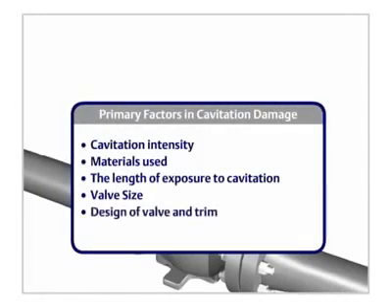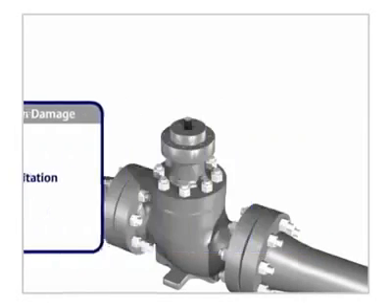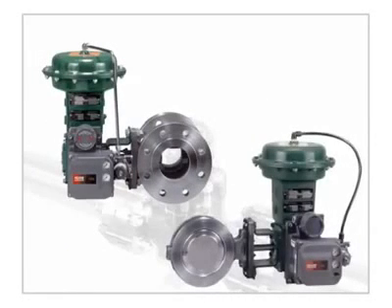The design of the valve and trim in the area of cavitation. High recovery ball and butterfly valves are more susceptible to cavitation damage.